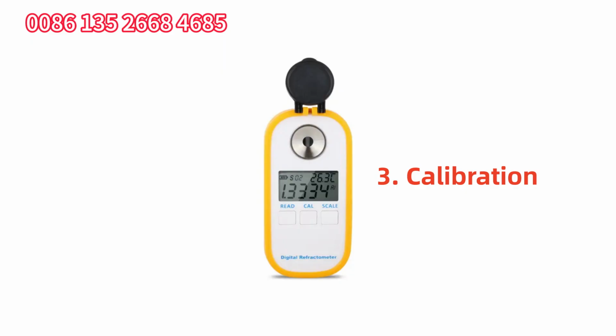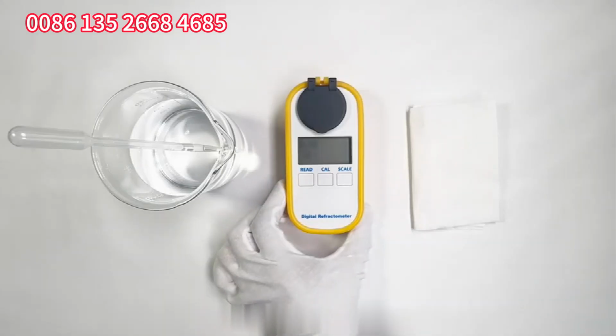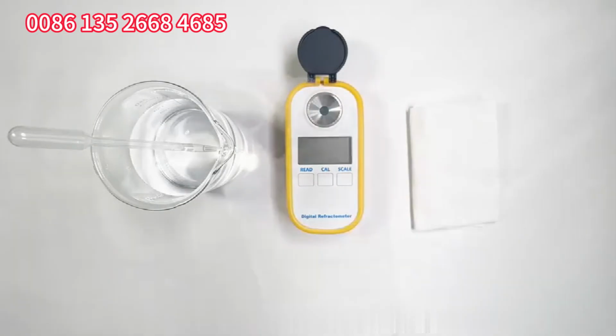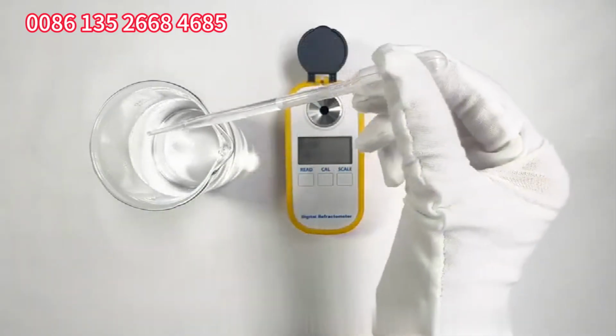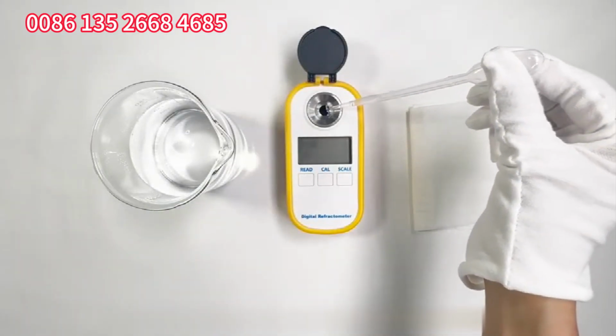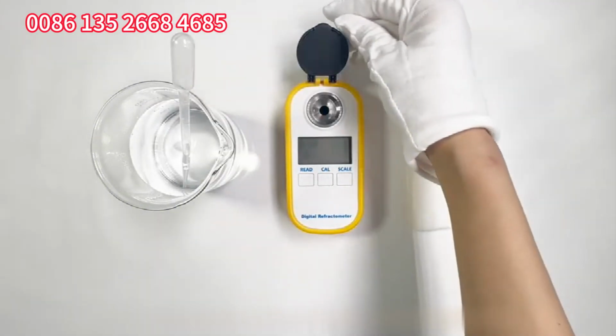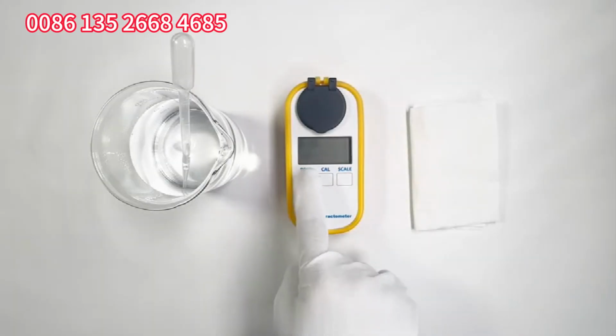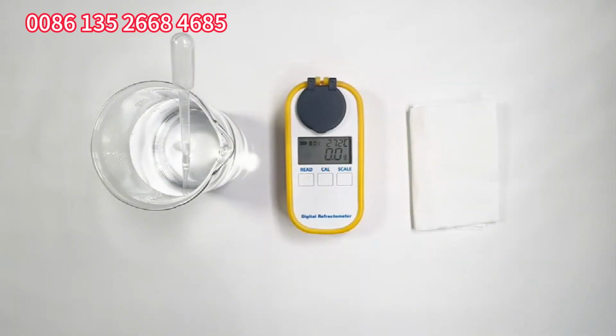Step 3. Calibration. This device can support calibration with pure water. Open the light shield. Use the pipette to drip 0.2 milliliters of pure water. Make sure the water completely covers the prism surface. Close the shield. Press the read button to power on.